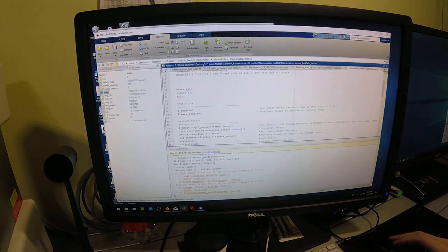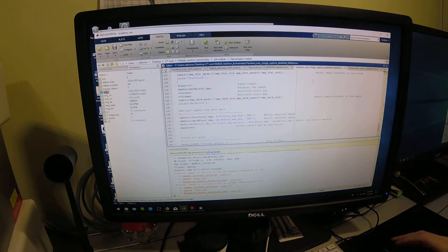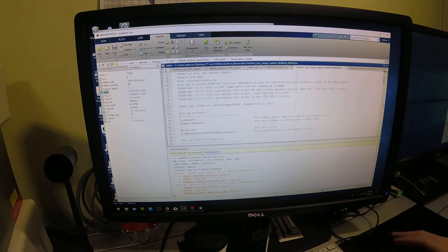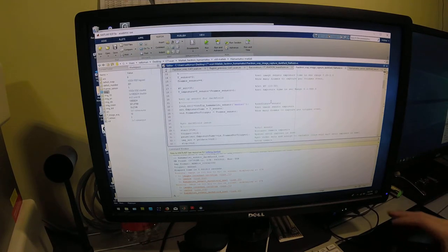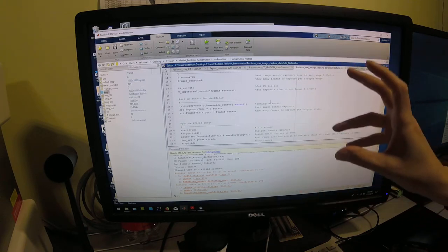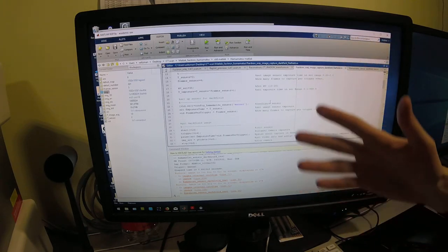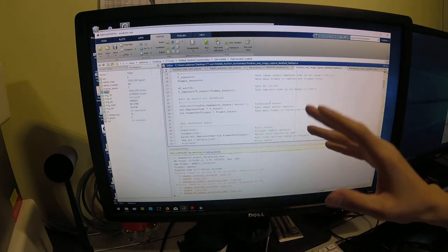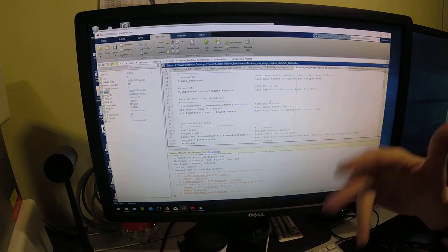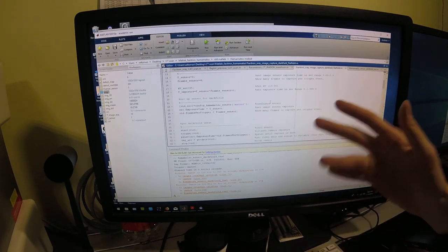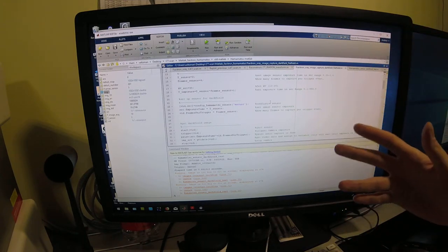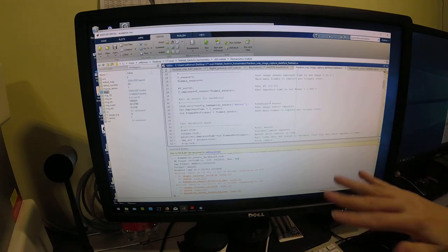The next thing to do would be a dark field and flat field capture. What this code would do is take the same dark field image as before, and then take the same images with the X-ray generator on, but without any object being X-rayed. This would just be a flat field, and it would correct for any inhomogeneities in the X-ray beam due to such things as a heel effect or any other alignment issues, or the presence of the carbon fiber plate that's protecting the image sensor.